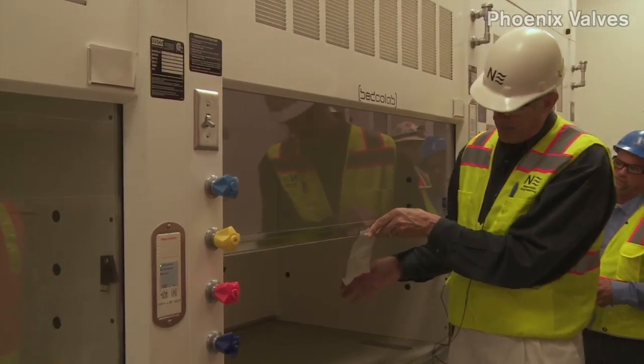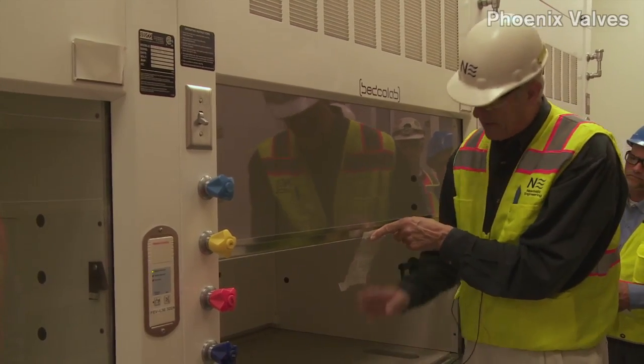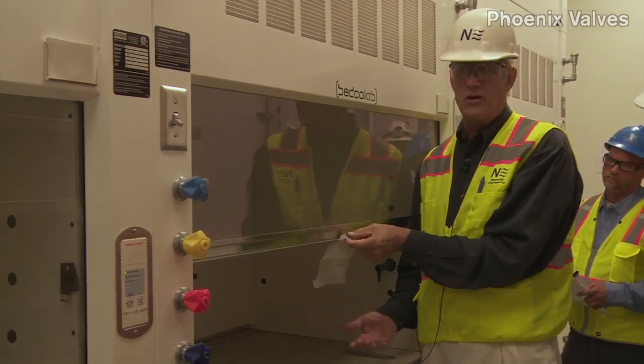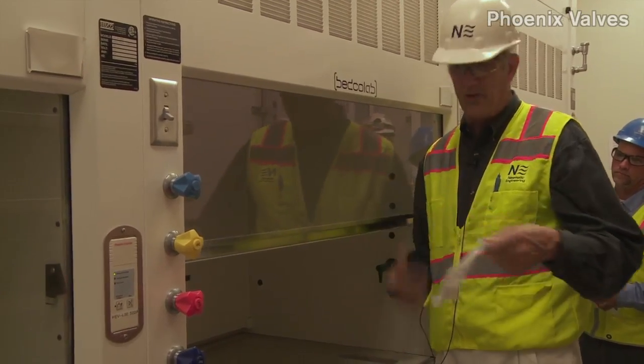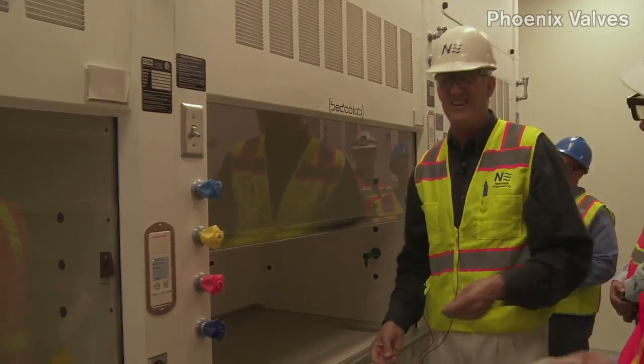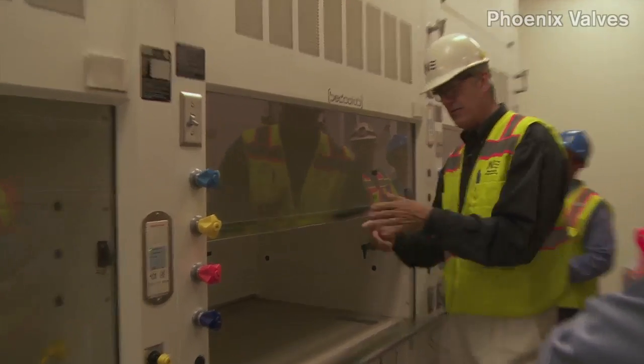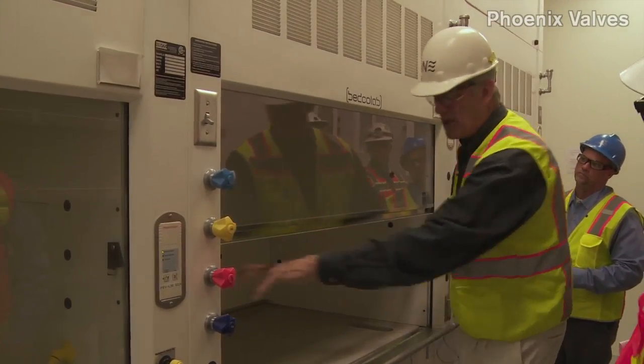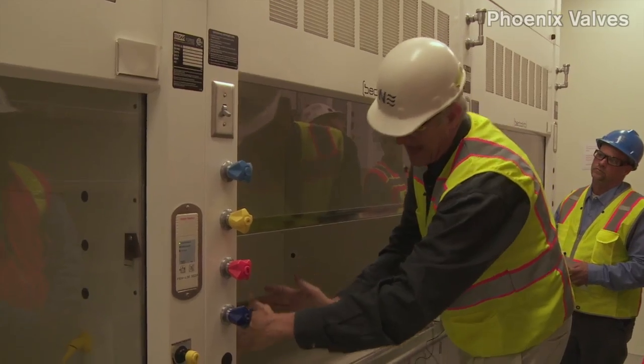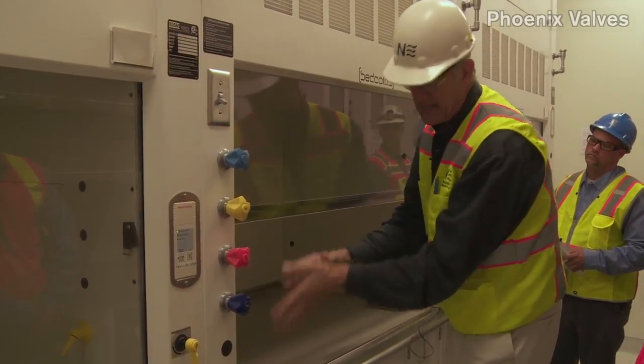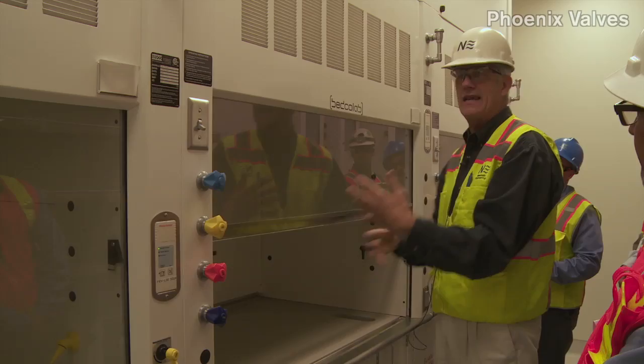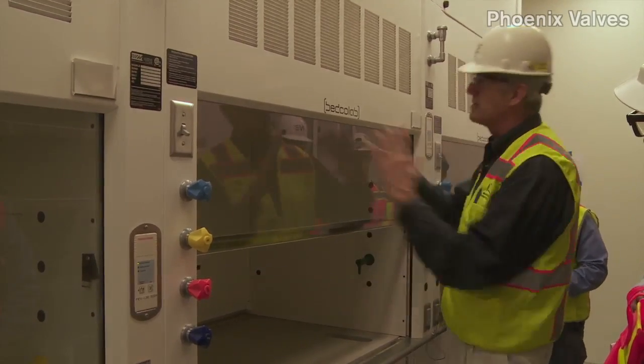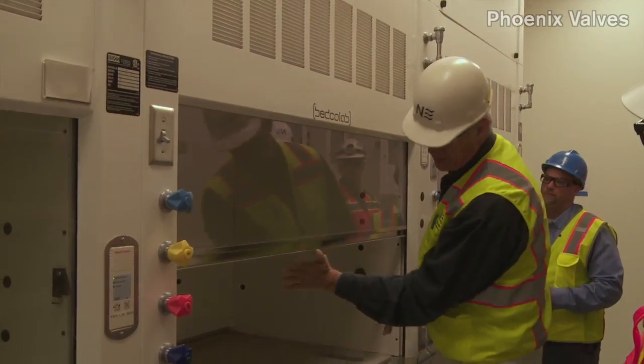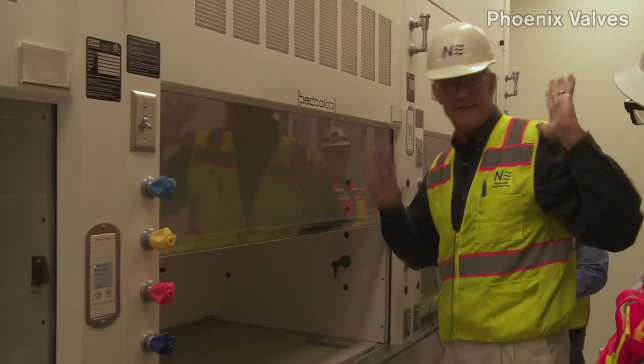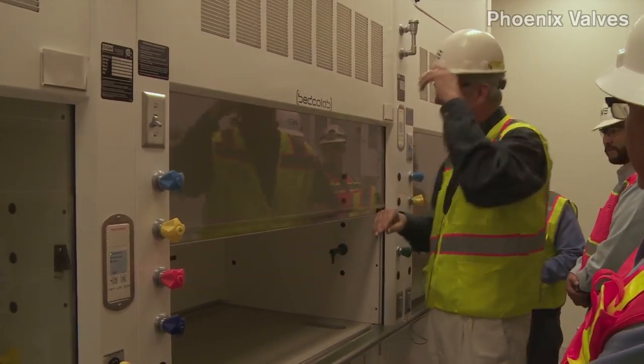And so when you open the sash, you want to see about a 40-degree angle going in, and you know the hood's operating right. I trust that more than any monitor on any side. The guy said, I'm sucking fumes. Well, there's things they can do. If they put equipment right in front and don't put it up on blocks, it'll block the airflow and you'll get dead zones. So there's things they can do in the operation of the hood that can affect how it works. But in terms of the mechanical system, if it's pulling in at a 40-degree angle, you say, hey, that hood's doing what it should be doing.